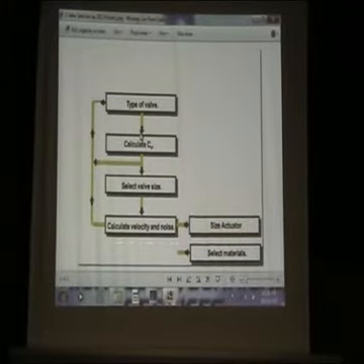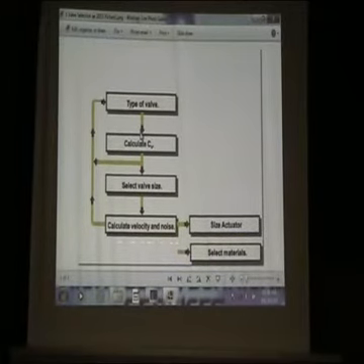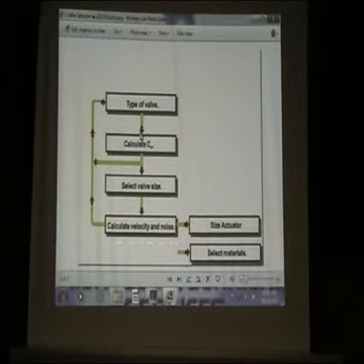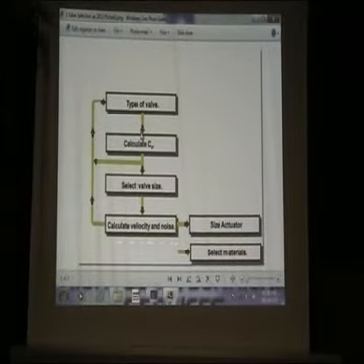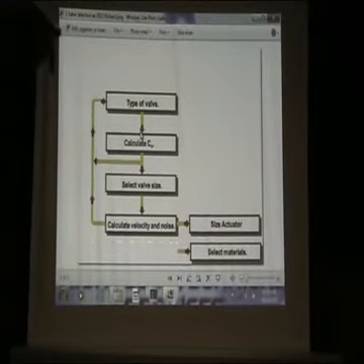And last thing, another thing that helps is usually the line size. I'm sure you handled that in your data sheets presentations the previous time. The line size is a very good indication for the valve guys of what material to use on their valves and also more or less what size. So if this is a 3-inch line, we know a valve that can handle 3 inch, and then you take it further by looking at all the other stuff. And then pressure drop across the valve is very important. Can this low pressure valve handle that pressure drop? No. Can that globe valve handle it? Yes, if you put different trims inside there to accommodate it. But that's a next presentation on globe valves.